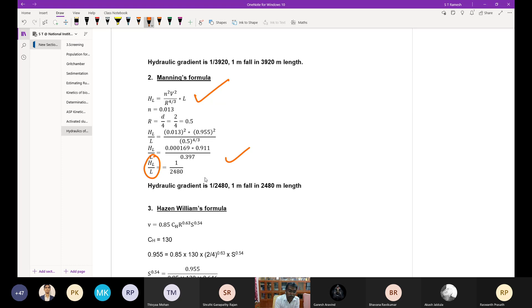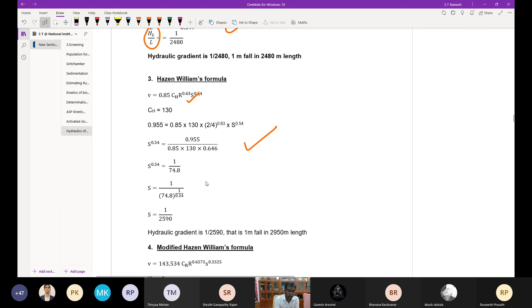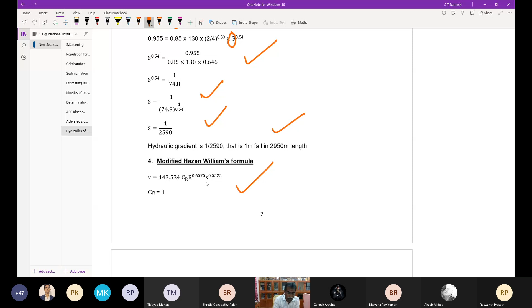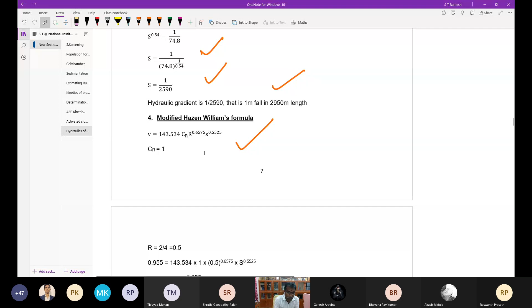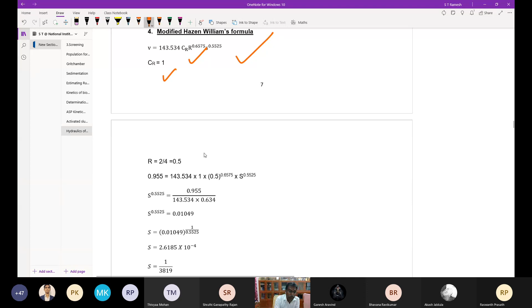And the third one is the Hazen-Williams formula. You can use this formula: V is equal to 0.85 CH R power 0.63 into S power 0.54, where CH I assumed as 130. All the values are known, and you just find out what is the slope, the hydraulic gradient. Here it is about 1 by 2590. And you can use the fourth formula, the modified Hazen's formula, and use directly whatever you have solved in the formula discussions. Take out the values from the table column, calculate the required parameters, and find the hydraulic gradient value.